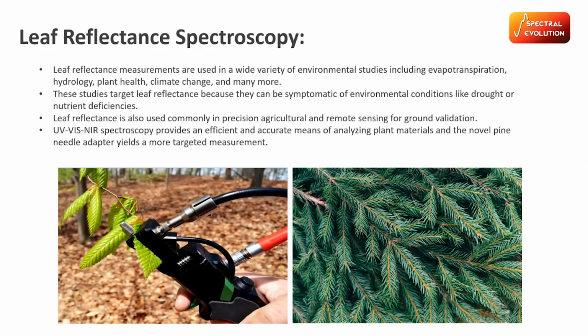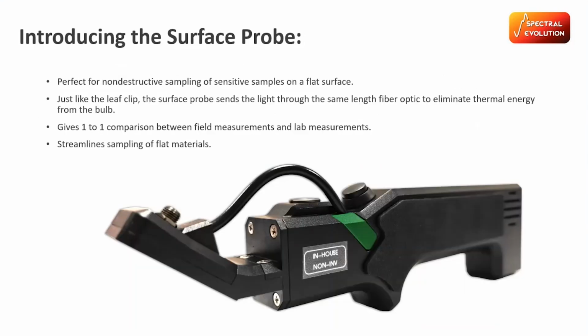And what we're introducing today is our new surface probe. The surface probe is a non-destructive sampling method. Similar to the leaf clip, it has an integrated tungsten halogen light source in the handle, and that light is sent through a fiber optic cable so that it eliminates any of the thermal components reflecting off of your leaf. So you're not going to dry out your leaves, and you're not going to damage them through prolonged sampling. This accessory is made to be a one-to-one comparison between field measurements and lab measurements. All of the optical geometries and the light source are maintained between the leaf clip and this surface probe, so you can put it directly onto your samples.